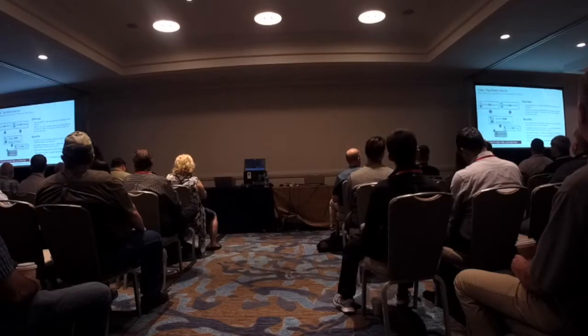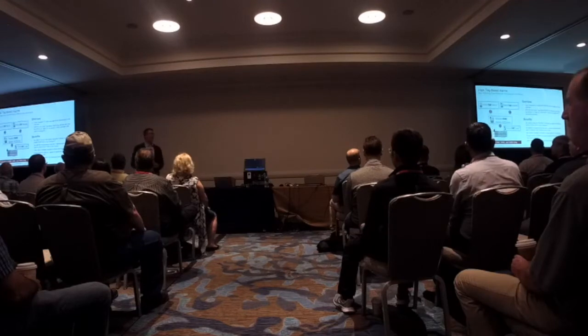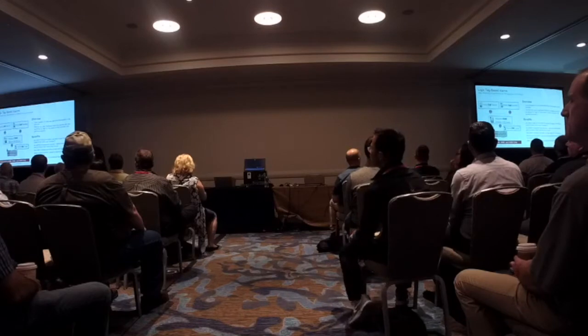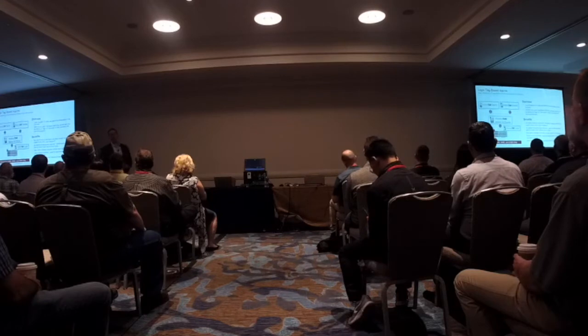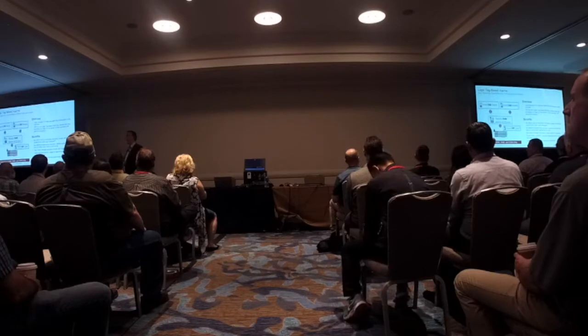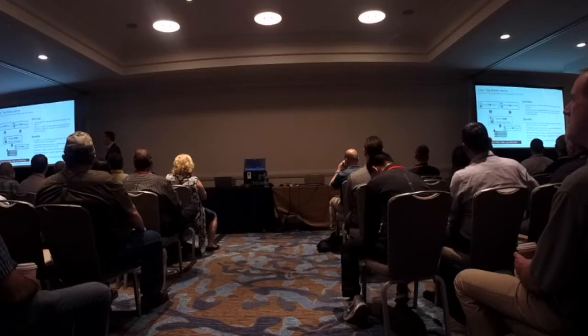As you may have heard this morning in the keynote with Ted Hill and the Rage energy drink demonstration, Julie demonstrated this new Logix tag-based alarm capability. This is a new capability where we simplified alarming in the Logix controller. We've added a new type of alarm called a Logix tag-based alarm. This alarm allows you to simply click on any tag in the controller, make it an alarm, give it a name, configure it, and that tag will monitor in the background. It doesn't impact the memory size or the execution of your controller.